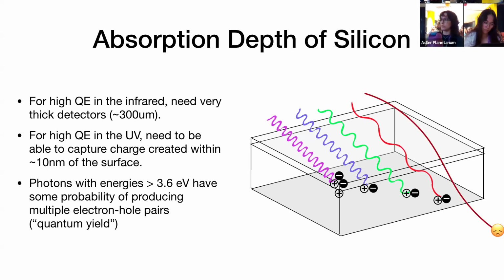If you want to be sensitive to near infrared photons at 1 micron, you need really thick detectors because they have a very low efficiency for converting into photoelectrons. On the other hand, very short wavelength photons convert almost instantaneously at the surface of the CCD. So ideally you want your CCD to be sensitive to both: the photons converted right on the surface and the ones that pass almost all the way through the CCD.